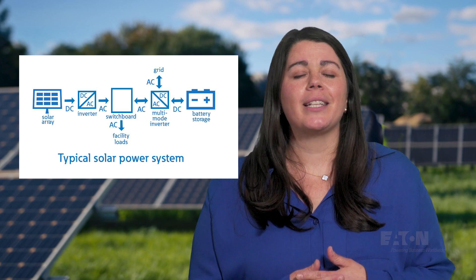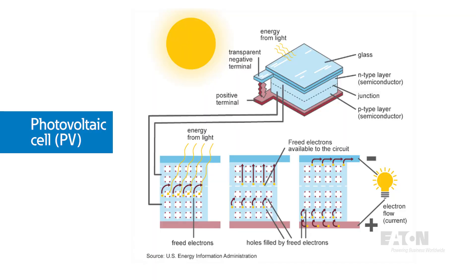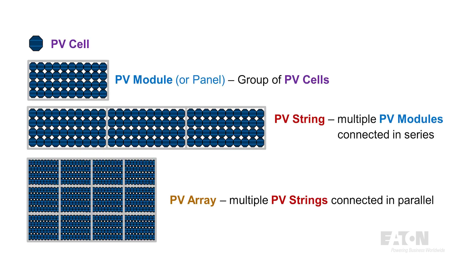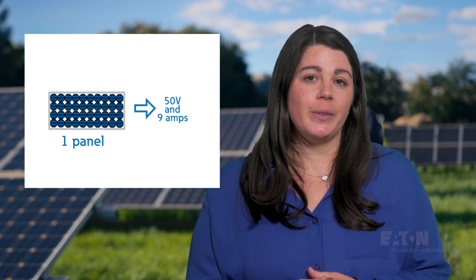Why do energy transition applications use DC? Because the generating and storage methods are only possible with DC. Even though this power is almost always converted to AC for distribution and consumption, the source of the power is DC. Let's use solar as an example. A photovoltaic cell is an electronic device that converts light into DC electricity. A single cell doesn't produce much energy, but can be wired into groups called modules or panels. Typically, one panel will generate less than 50 volts and 9 amps.